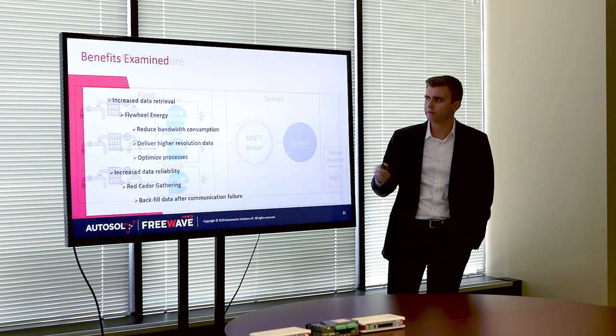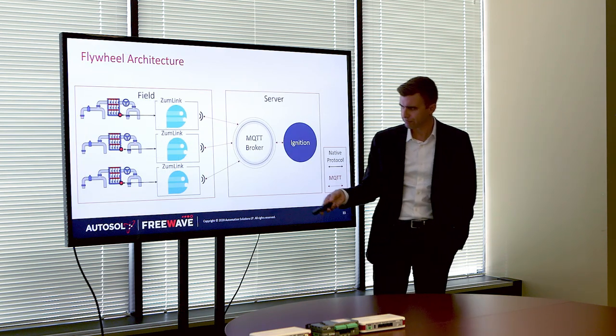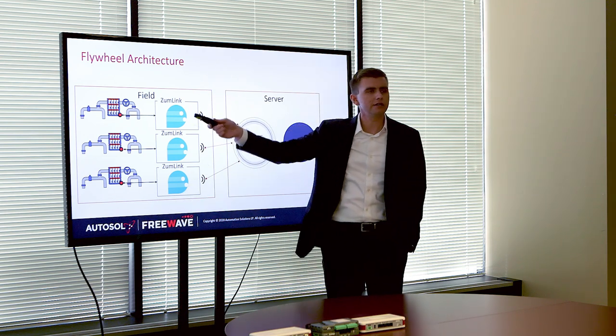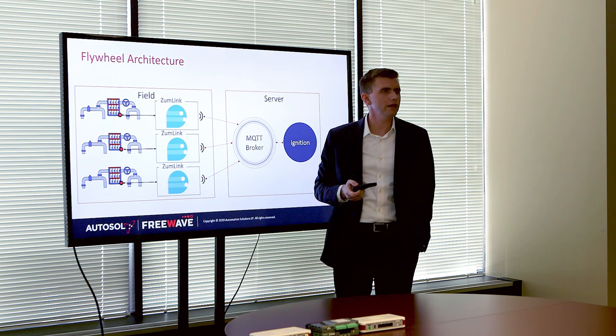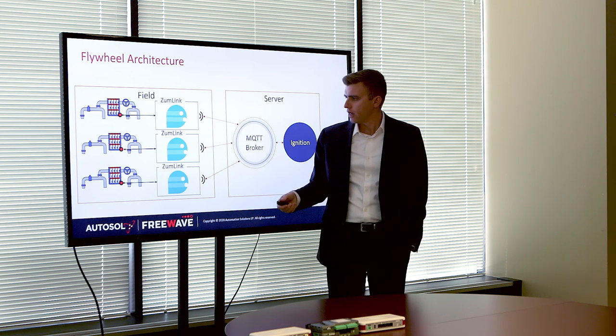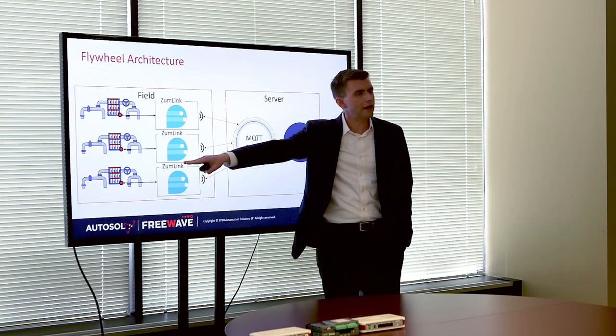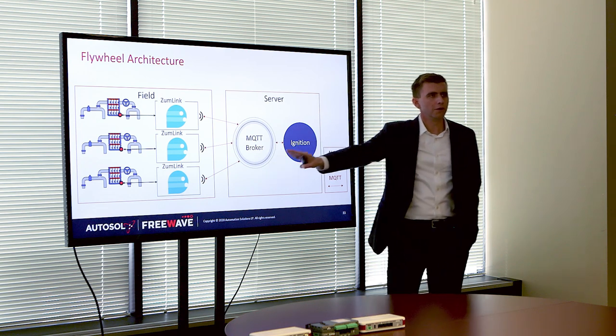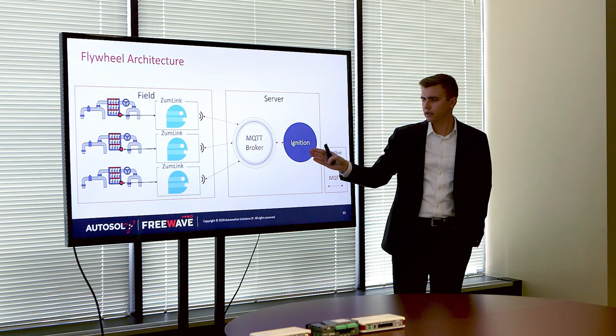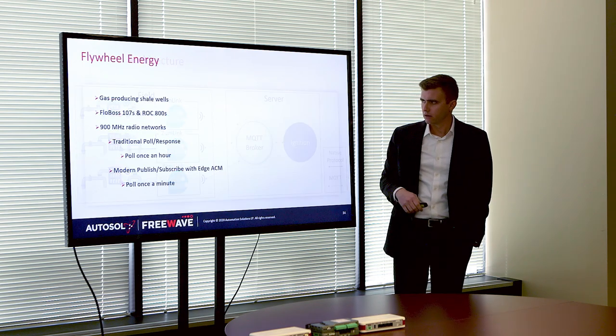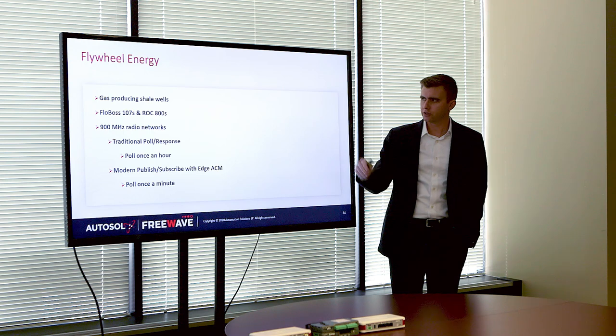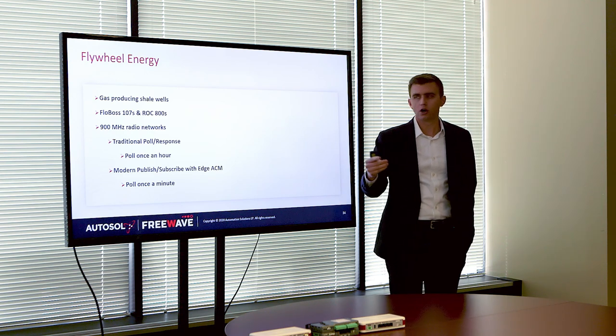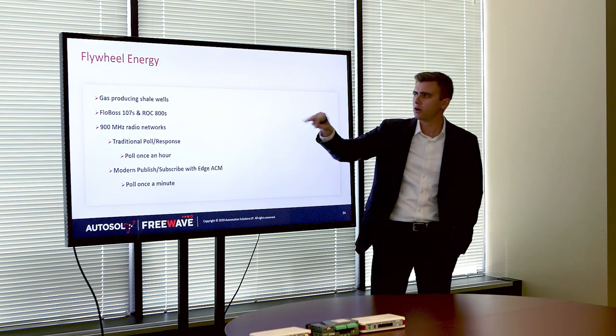This is Flywheel's architecture. They have ROCs out in the field and are replacing their radios with ZumLinks with Edge ACM already installed on them. Edge ACM is pulling thousands of tags on each ROC, publishing via MQTT to a broker where it's being natively consumed via MQTT SparkplugB in their Ignition HMI. They have gas-producing wells with two types of devices that have plunger lifts: FloBoss 107s and ROC 800s, about half of which are serial.